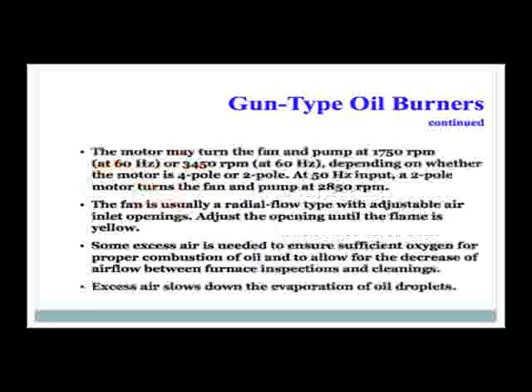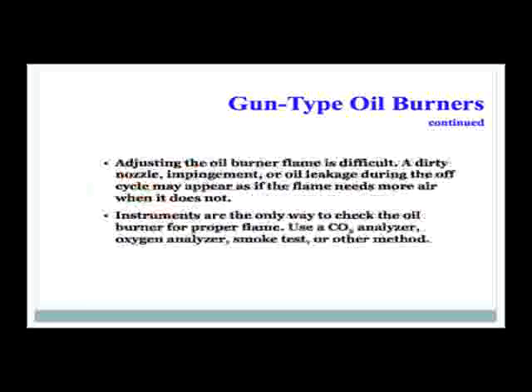Excess air slows down the evaporation of oil drops. Adjusting the oil burner flame is difficult — a dirty nozzle, impingement, or oil leakage during the off cycle may appear as though the flame needs more air when it does not. Instruments are the only way to properly check the oil burner flame. Use a CO2 analyzer, oxygen analyzer, smoke test, or another method.